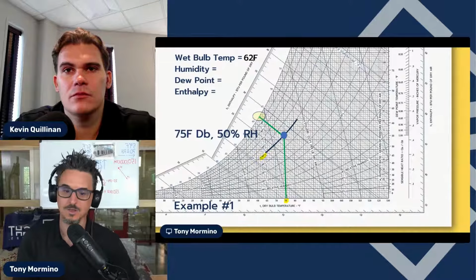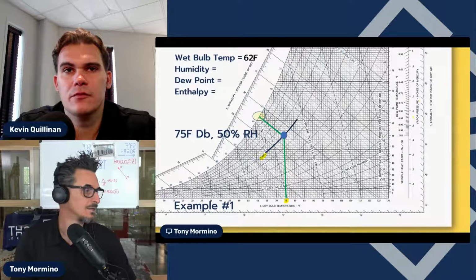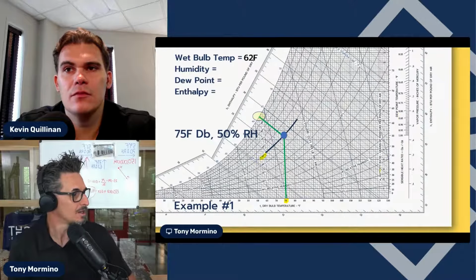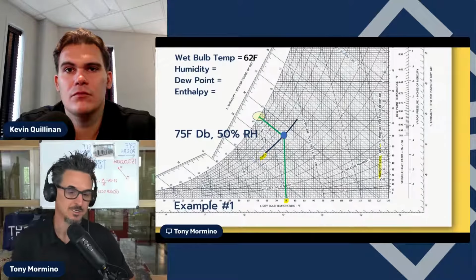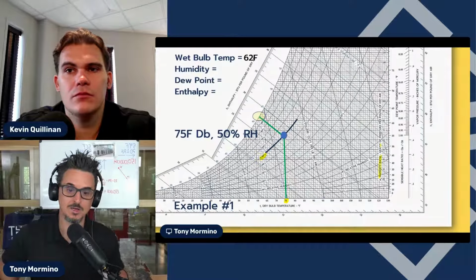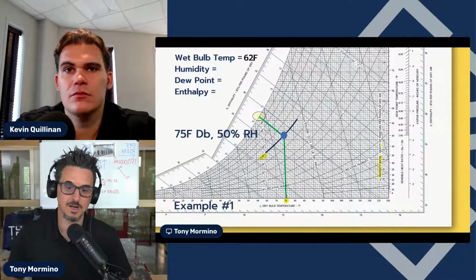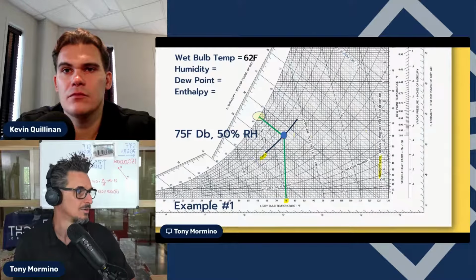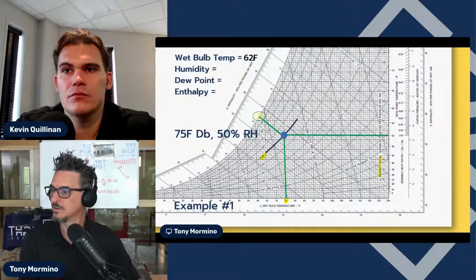Okay, so what about the humidity? The humidity is represented on this chart by the grains, called humidity ratio. Some charts just call it humidity, which is the grains per pound of dry air. So what you would do is just draw a line from that point using your straight edge over to here, and you'll see that the grains are 65.